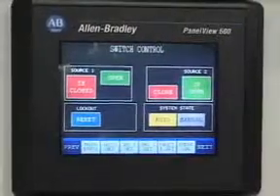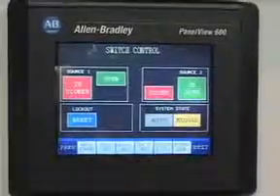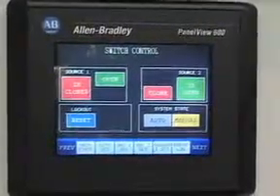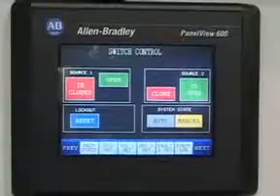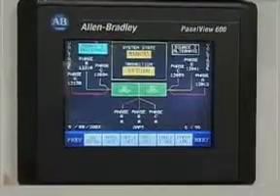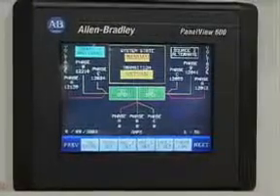It's all running automatically. To operate it manually, I would simply push on the button, the device changes to manual, and now I can operate one of the switches. I'll operate source 1 open right now by just touching the button. And now we see the system state has changed. It's showing source 1 is open, source 2 is open. And if we go back to the main screen, you'll see both our switches are open now. It shows we are in a manual state.